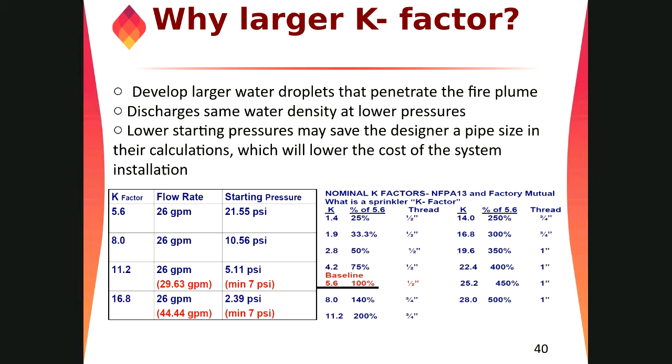This does not mean exactly the minimum pressure. The minimum we need at the remote location is 7 psi. Maybe at the remote we calculated 7 psi, but if the fire just started at the beginning of the riser, there we may get 30, 40 or 50 psi. We don't have any problem with that as long as we are getting those flows and pressures.